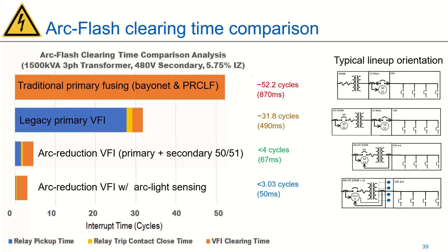Mm-hmm. So, yeah, very good question. High resistance grounds or resistance grounds are often used to mitigate some of that arc fault energy, or rather the ground fault energy that's coming back through. And in the integration of this, those 50/51 relays often have a neutral CT input as well. So I would suggest, if you do have an NGR or something like that, that you incorporate that neutral CT so you can sense that directly.